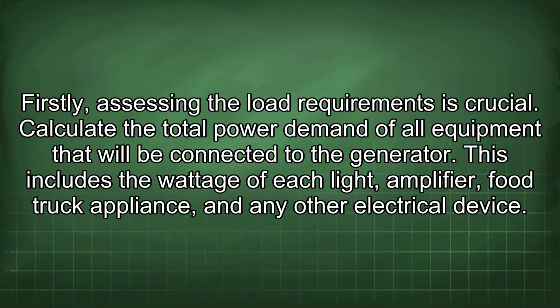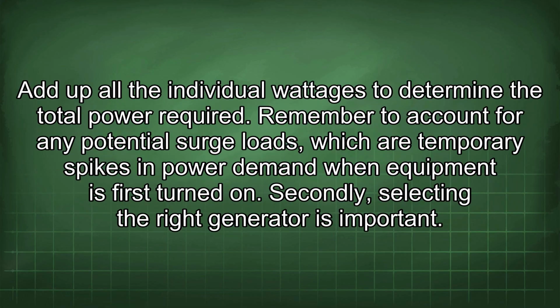Firstly, assessing the load requirements is crucial. Calculate the total power demand of all equipment that will be connected to the generator. This includes the wattage of each light, amplifier, food truck appliance, and any other electrical device. Add up all the individual wattages to determine the total power required. Remember to account for any potential surge loads, which are temporary spikes in power demand when equipment is first turned on.